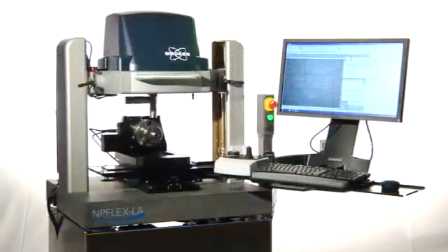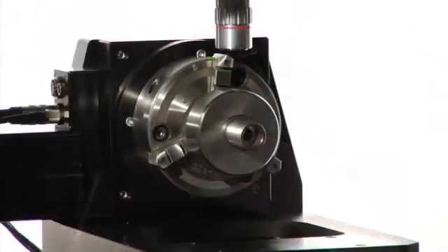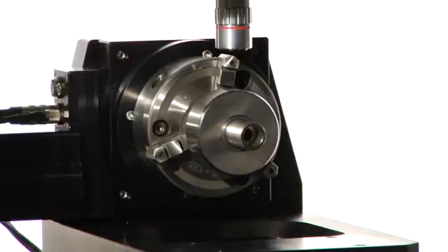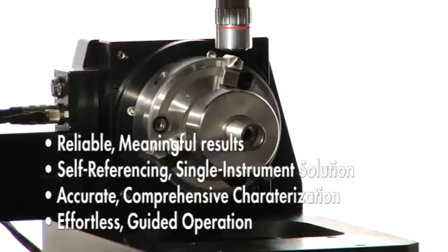With patent pending algorithms and method for calculating lead angle, the NP-FLEX LA provides accurate measurements without concern for part alignment and level. Taking advantage of Bruker's patented optical technology, the NP-FLEX LA utilizes the latest advances in white light interferometry to provide meaningful, accurate, quantifiable characterization of the sealing surface.